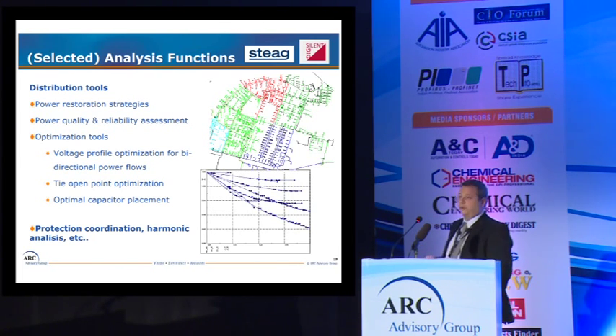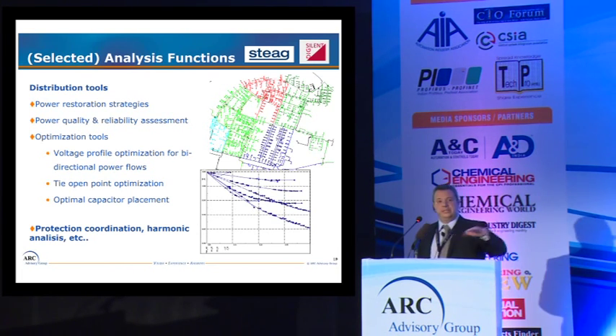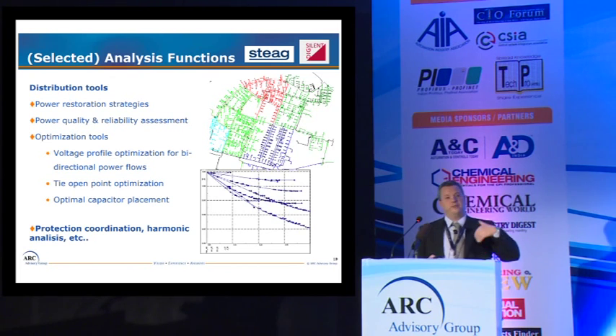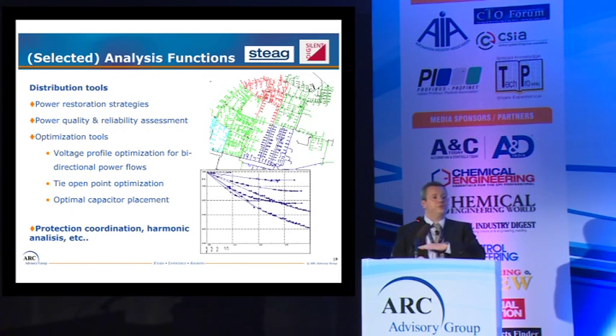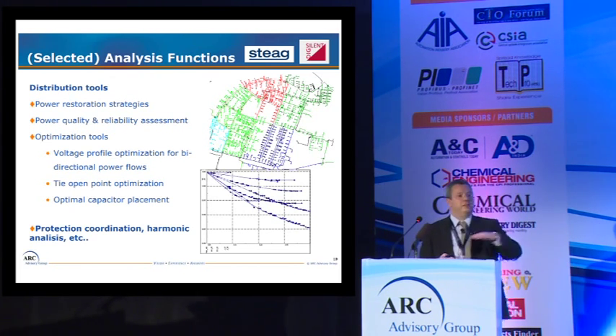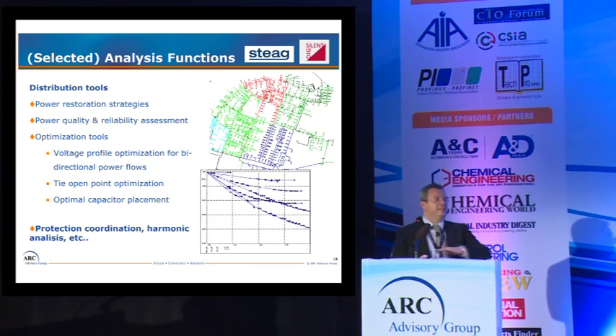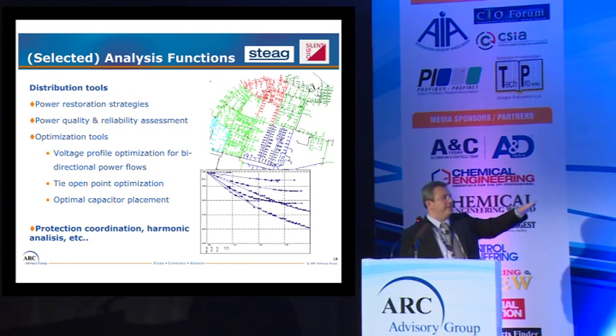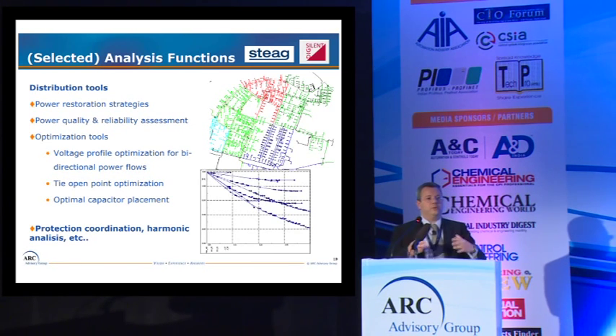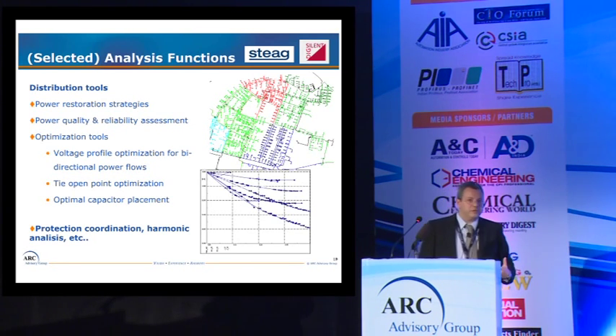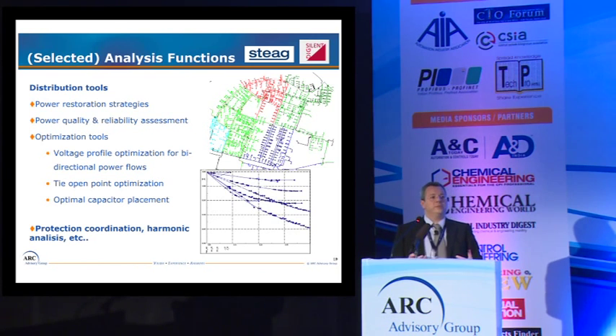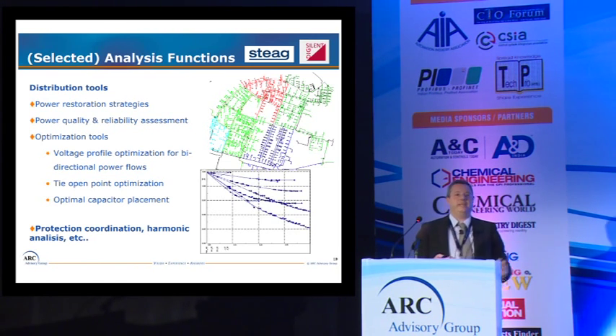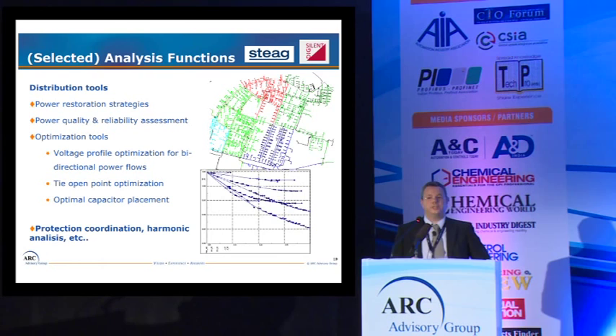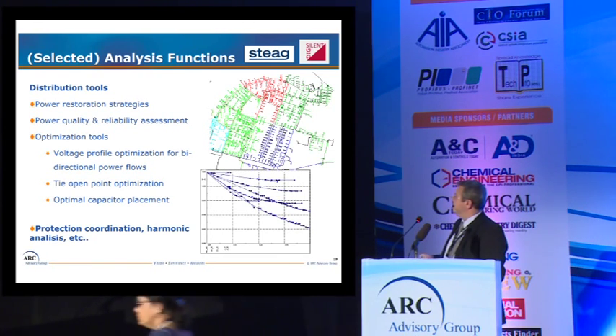Also optimization tools. For example, depending on the hour of the day, if you have more or less PV generation, instead of the classical voltage drop along the feeder, the voltage may actually go up towards the end of the feeder. So you need to work out the optimal tap position of your secondary transformer so that throughout the day the voltage stays within the allowable limits.